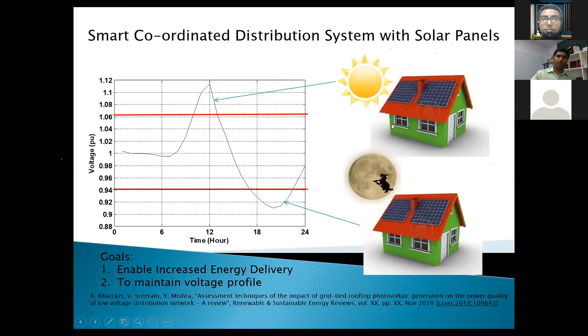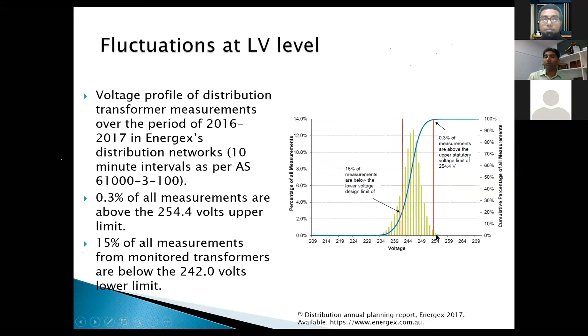We wrote a good review paper about all the problems that grid-tied rooftop small-scale photovoltaic generation is causing recently. This is data from one of our distribution utilities, and you can see the voltage is all over the place. You can see how it should be, and how much high voltage these feeders are facing on a regular basis. It should be 240, and the voltage can go up to 254.